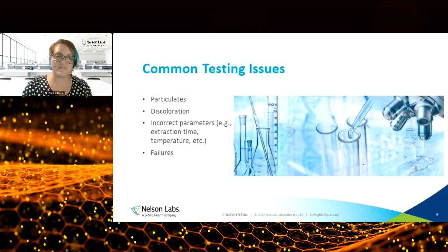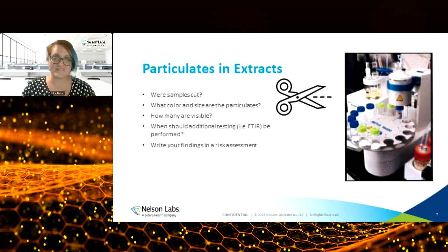The first thing I want to cover today is some of the most common issues that we see as biocompatibility experts when we're consulting sponsors. The first one, which gets a lot of questions from regulatory bodies, is particulates found in your extracts after performing the extraction. Another common one is discoloration, which can happen in multiple samples or only certain samples. The third is incorrect testing parameters being selected, because whatever you tell the lab to use for the extraction parameters, that's what they'll use, and they might not be the right ones for your device. And the last thing I wanted to talk about is failures. So to start us off, we have particulates in extracts.